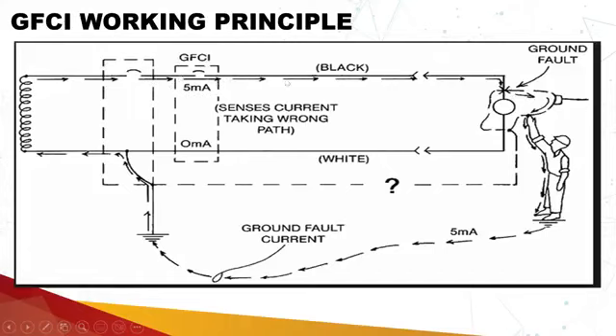But the GFCI will trip on the 20 ampere if there is a difference of 5 milliampere, 10 milliampere, whichever you have set. And the GFCI will also trip if the socket has a capability of 20 ampere and you are running a load of only 5 ampere, but there is some leakage current there. The GFCI will pick up that current and isolate the circuit.